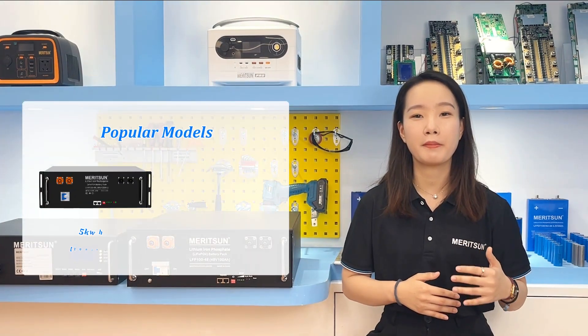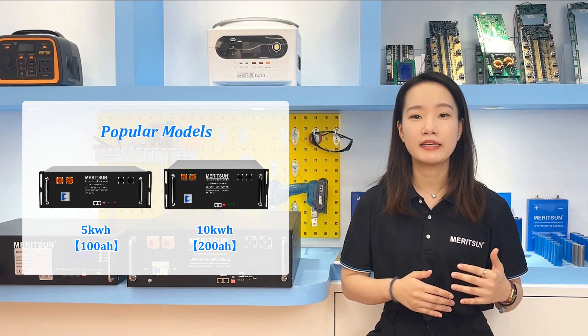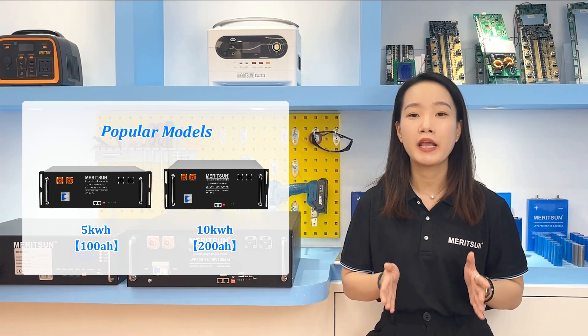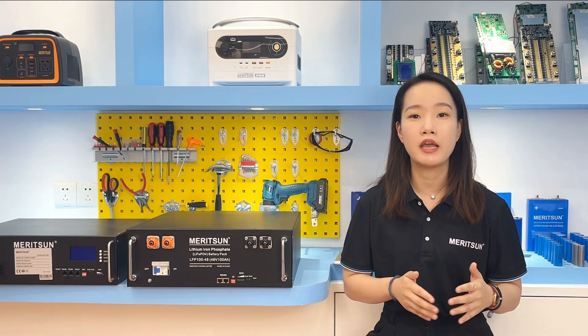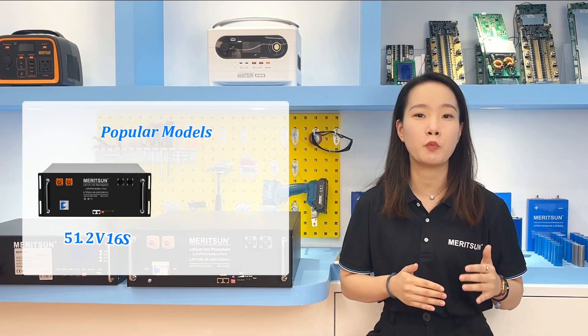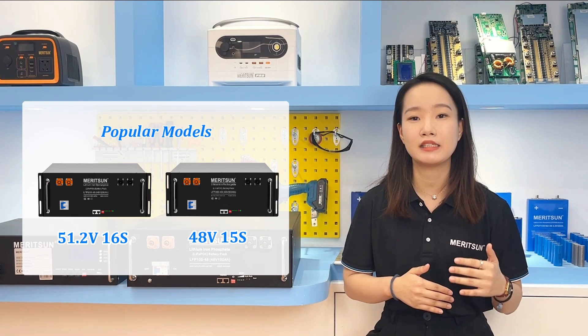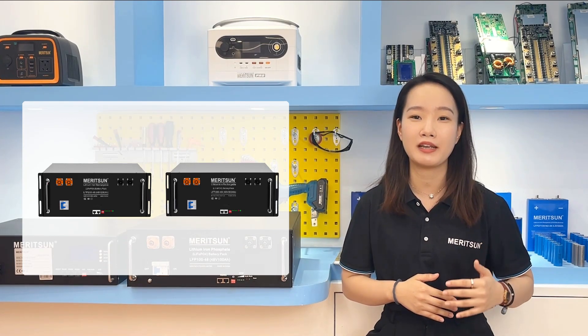Popular models of rack-mounted batteries are 5kWh and 10kWh, namely 48V 100Ah and 48V 200Ah. In order to adapt to the working voltage range of some inverters, the market also uses 16 × 3.2V batteries, namely 16S, representing 16 cells in series, which is also used for the 48V system.